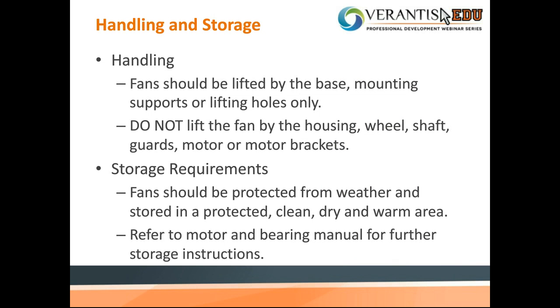So, handling the fan, how should I pick this thing up? It's pretty simple. If it's inside of a crate, you can just use a forklift or a tow motor or something to lift it up. But if it is out of the crate, fans should be lifted by the base, mounting supports, or lifting holes. If you order a custom fan, it may include lifting lugs or lifting eyes, so you can properly pick it up that way. By all means, do not lift a fan by the housing, the wheel, the shaft, the guards, or the motor bracket. These are all important components that are key to the operation of the fan. If any of these components are compromised, you run the risk of a failure in the field. So definitely handle these things properly. They're pretty robust pieces of equipment, but they still need to be handled properly.